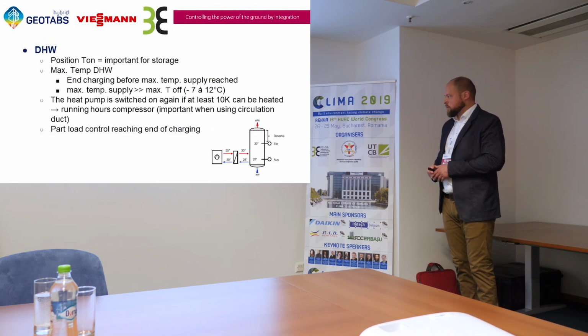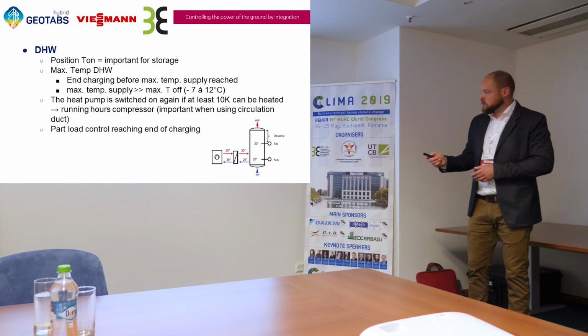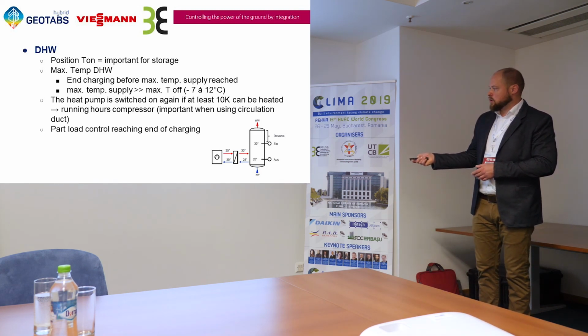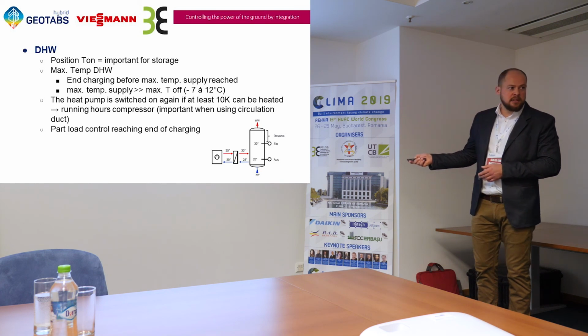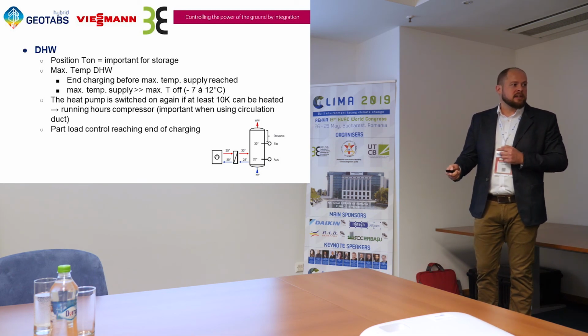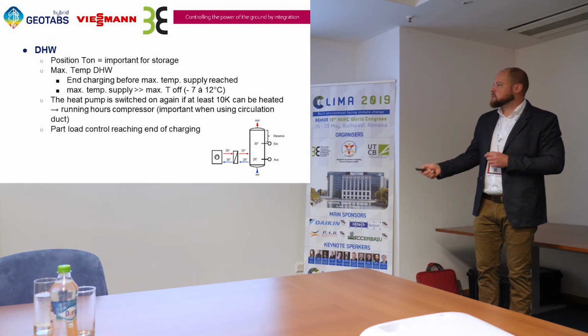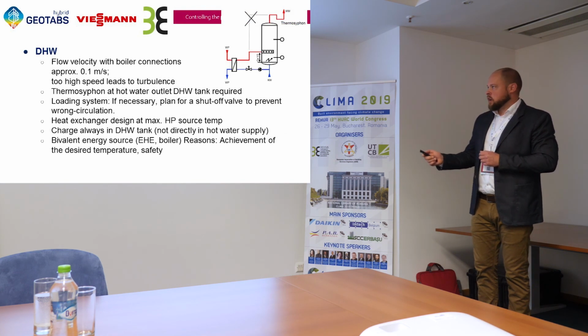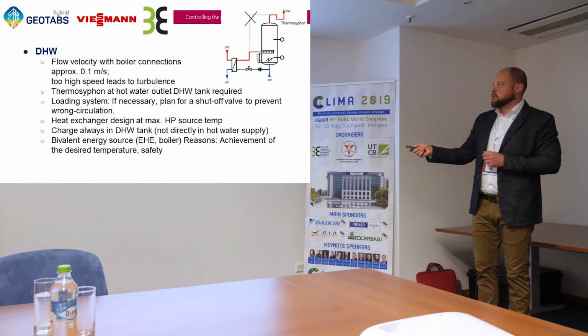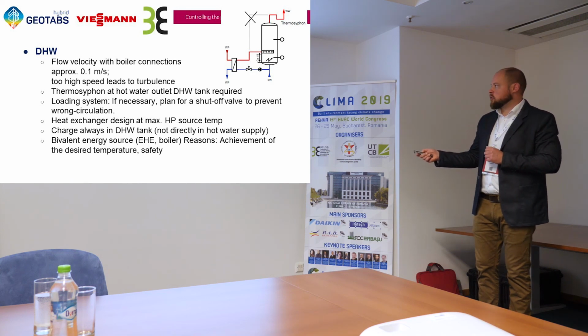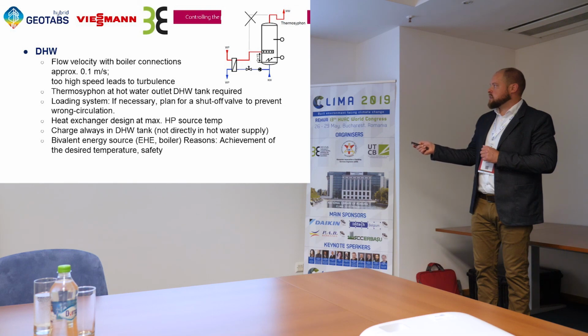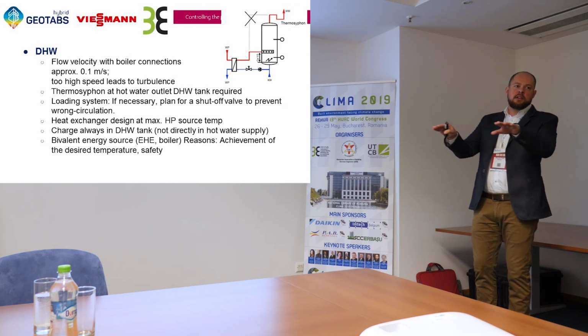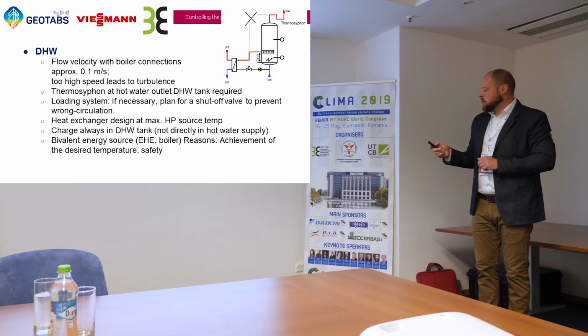Here you can see some temperatures, why it's important not to charge the domestic hot water tank on top with a normal system, because when we have a return temperature of 28 degrees, the departing temperature is only 33 degrees. And when you inject that on top of the buffer tank, it gives a problem in the domestic hot water production, of course. So there are some different systems. Also we speak about a maximum flow rate of 0.1 meter per second on the incoming side to keep the stratification inside of the tank normal. We can use this type of pipe also inside. It deflects the incoming hot water in a plane, so it will keep the stratification correctly.